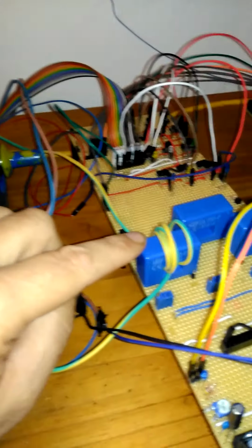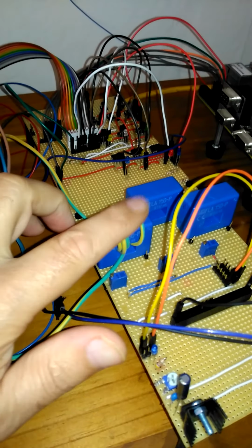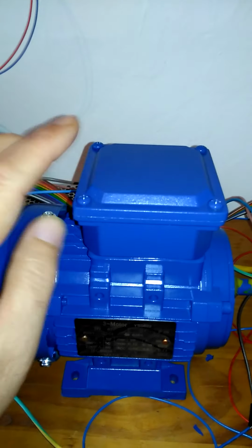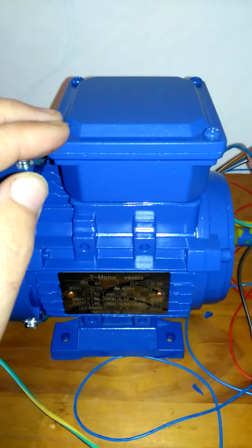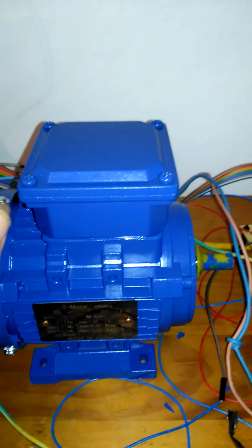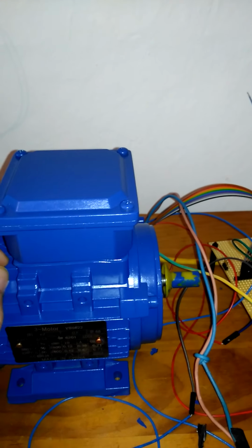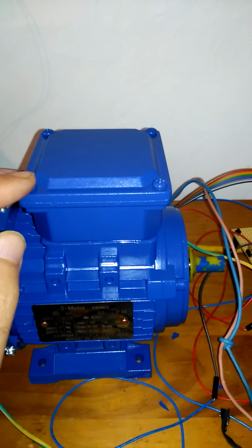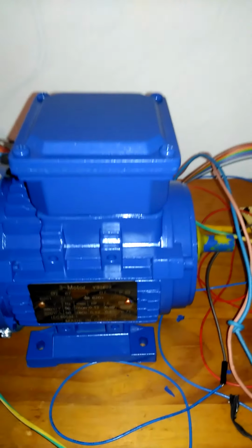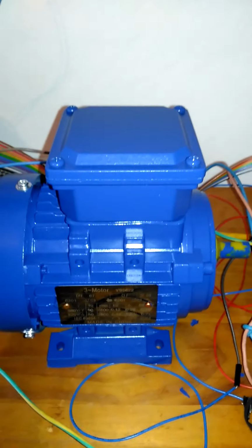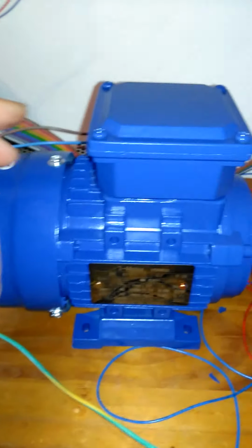At the moment, I'm going to be testing this Hall effect CT over here. I'm going to be reading some current via the primary. I'll do this by injecting a DC voltage into the stator winding, and then I'll do some calculations and work out the resistance of a single winding in the stator. Like I said, it's delta connected, so there's another calculation there, converting from delta to work out the single phase resistance.